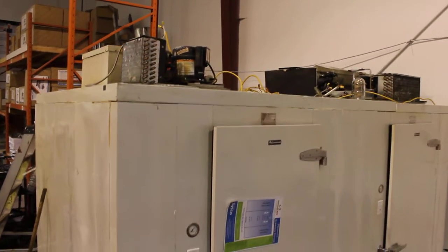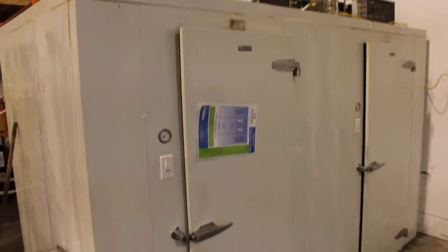Coldstream walk-in cooler freezer combo — we just pulled this out yesterday, got it plugged back in the shop to make sure everything's working okay. This one's holding at 5°, the freezer is holding at minus 13°. It was at minus 15° — I opened the door for a little while.